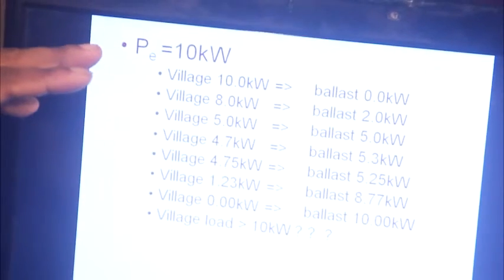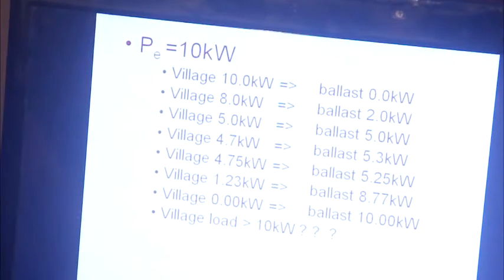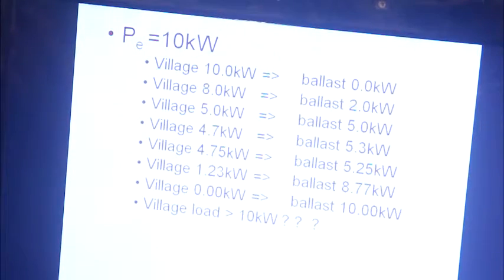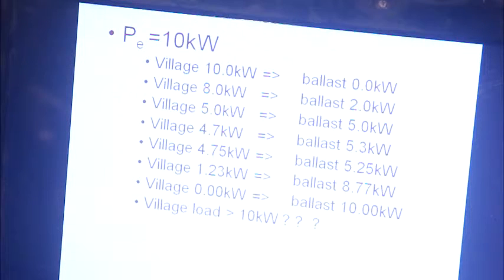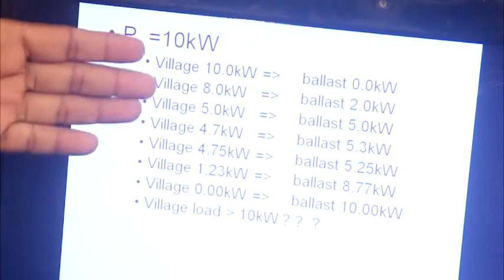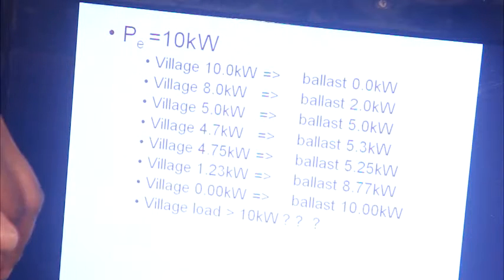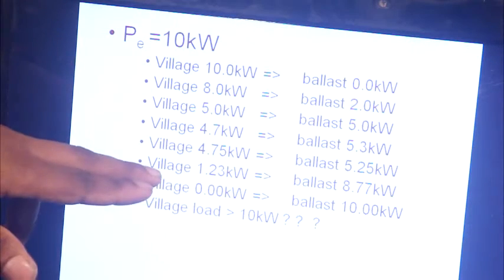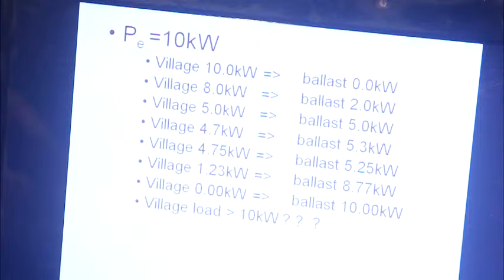Let's consider a 10 kilowatt hydropower project. If the village load is 10 kilowatt, the ballast excess power is 0 kilowatt, so no ballast is required. Whenever the village switches off 2 kilowatt, the village demand reduces to 8 kilowatt, and the ballast has to switch on exactly 2 kilowatt. If the village further reduces load to any value — 5 kilowatt, 4.7, 1.23, whatever — the ballast output should be exactly equal to the excess, so that village load plus ballast always equals 10 kilowatt.